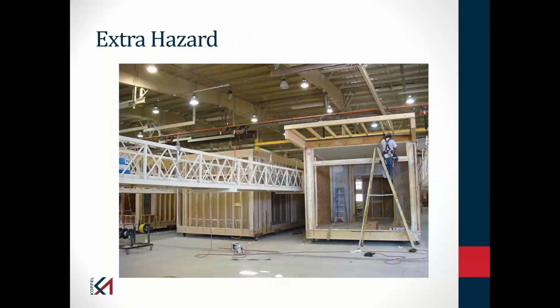Extra hazard, we tend to get into areas where we're likely to encounter combustible dust or quantities of flammable and combustible liquids. So again, some of your lab spaces or research areas might fall into the extra hazard classification. But I suspect most areas on your campus are going to be light hazard or ordinary hazard. So how does that affect you as a facility person? When somebody comes in and says, I want to change this office to some other use, one of the things that needs to be evaluated, and you might not be doing any construction, so you might not be pulling a building permit for this, one of the things that needs to be considered is, are we changing the occupancy, the hazard associated with that space? So that's the reason for going through this generic discussion.